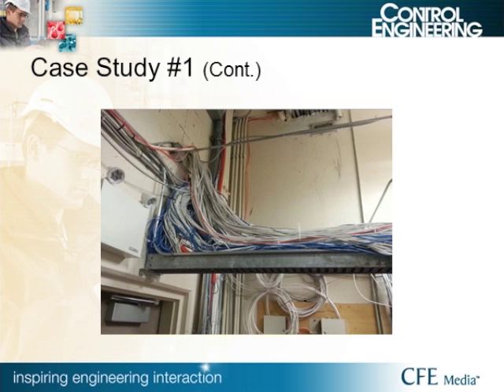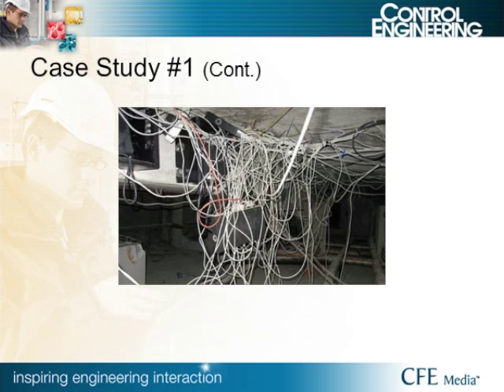This next example started off with a small wire way. There are several guidelines for how you should populate a wire way. Looking at an overfilled one, troubleshooting would be quite a challenge — finding which cable is where. And then my personal favorite, the 'poor man's distribution cabinet,' where switches are actually suspended by cabling. These examples show why your cabling structure and infrastructure need to be thought out beforehand.